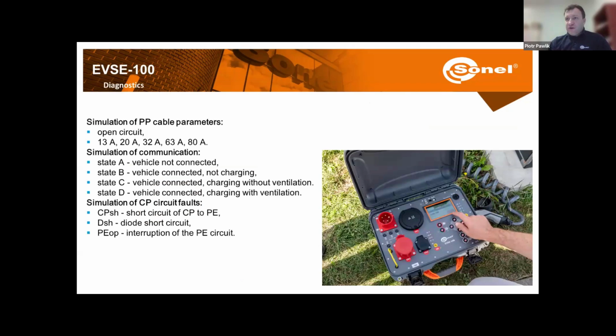Okay, so what can this meter do? What's the significance? First of all, I know that many manufacturers have adapters for checking charging stations. So you need some base meter, then you buy an adapter, and they work as a set. But here the EVSE100 is a standalone meter. So you just have one unit, and it's good for checking different types of charging stations. It can simulate different current levels on the proximity pilot, different states of the control pilot, so A, B, C, or D, and different errors on the control pilot, like you can see here in the picture.